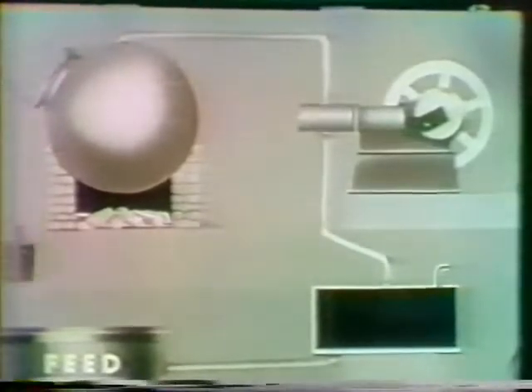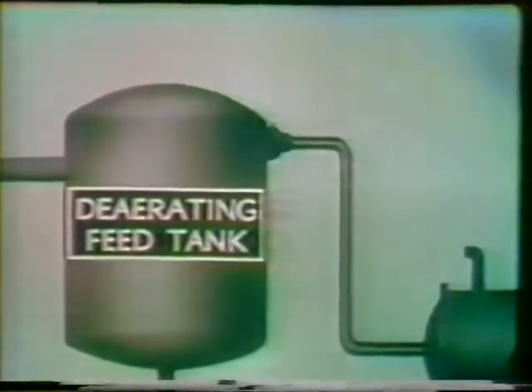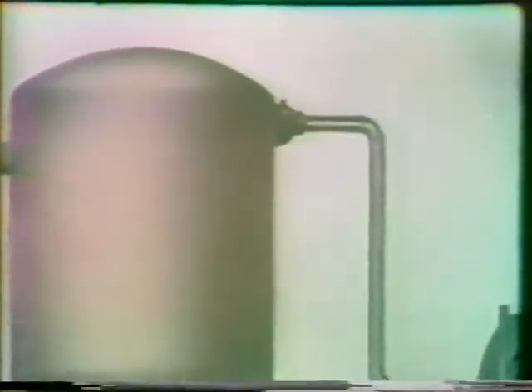As we saw in the early steam cycle, the final phase is the feed system. In the modern naval feed system, the de-aerating feed tank does a big part of the job. For one thing, the de-aerating feed tank acts as a reservoir to supply feed water to the boilers under all conditions. Another highly important function of the de-aerating unit is to remove any air still remaining in the water. At high temperatures, air corrodes boiler tubes like acid.